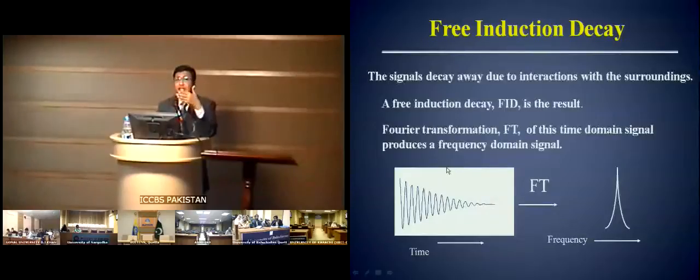NMR remains a technique in which human intervention is extremely important, either for pulse calibration, which I told you yesterday, or shimming of your magnet, because you need to have a homogeneous magnet, or locking a particular solvent, or having a reference of a compound like TMS and others, or removing the so-called phase errors, all of these things.